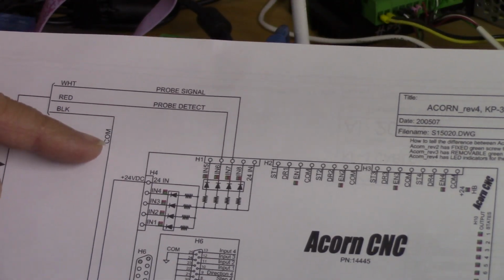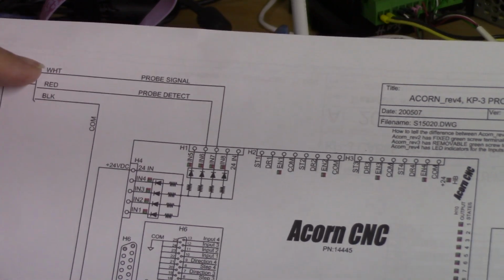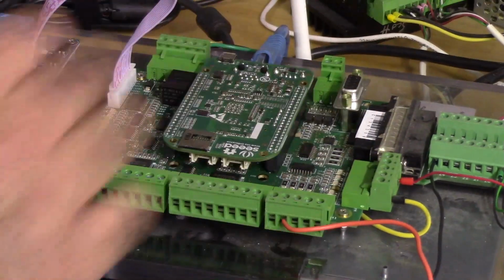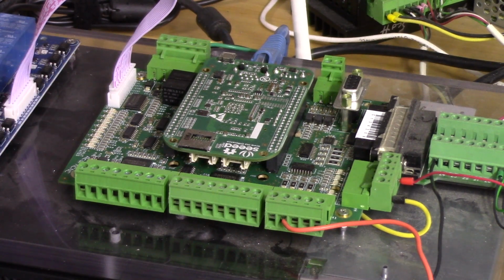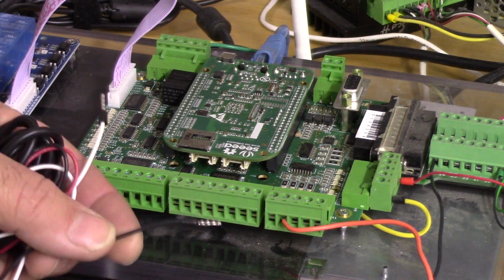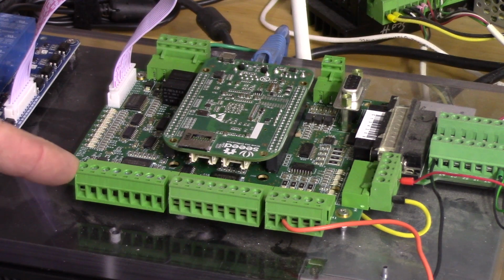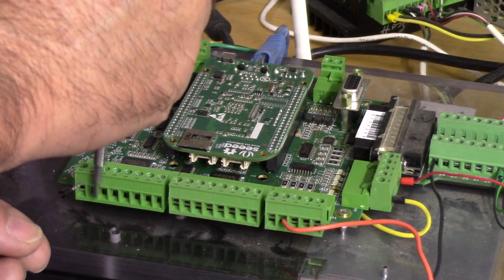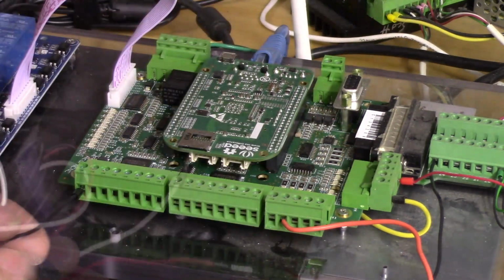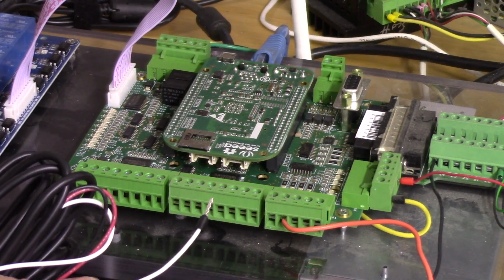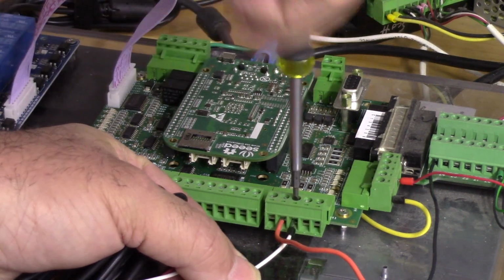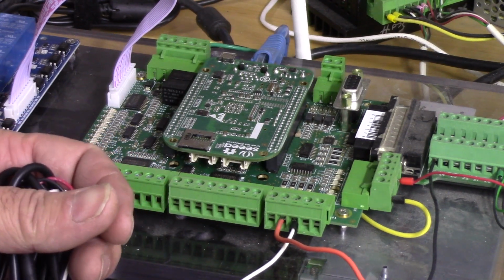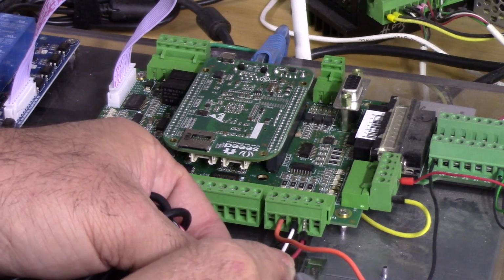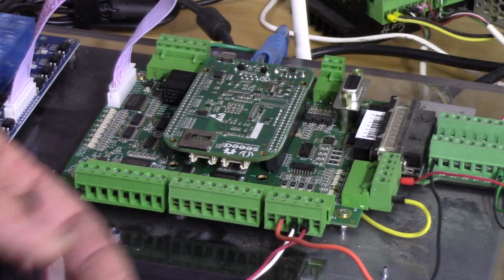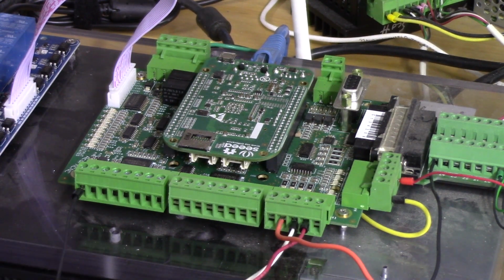Okay, according to the schematic, the black wire is going to go to common, the red is going to go to input 6, probe detect, and the white wire, probe signal, is going to go to input 7. Okay, my Acorn is powered down, and you don't want to be wiring anything up to Acorn while it's hot. So I'm going to take the black wire and I'm going to use the axis for COM terminal right here. And then our white wire is going to go to probe signal, input 7. And then our red wire is going to go to probe detect, input 6. Okay, so that's very simple, just 3 wires wired up that way.